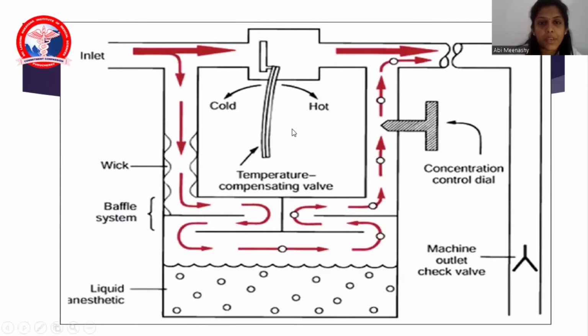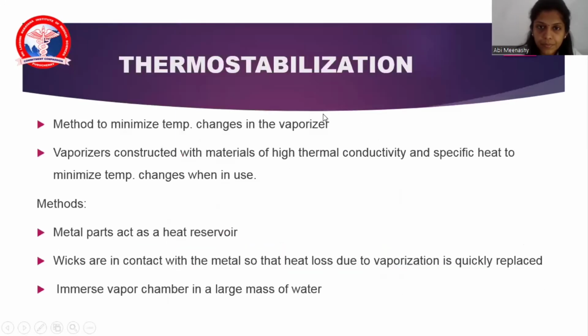Okay, we have a temperature compensating valve, so that the outside temperature doesn't affect your vaporizing chamber. So according to your control dial, this temperature compensating valve will go left and right. Okay, thermostabilization.